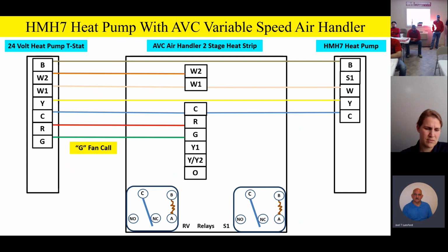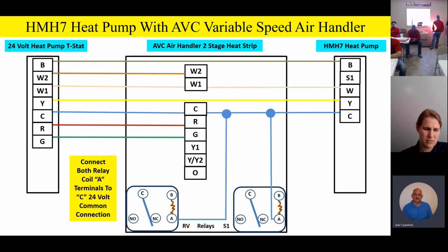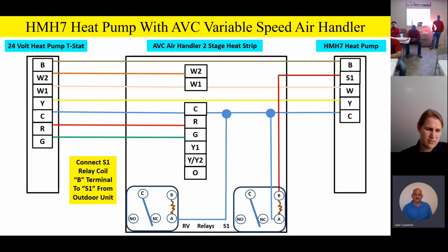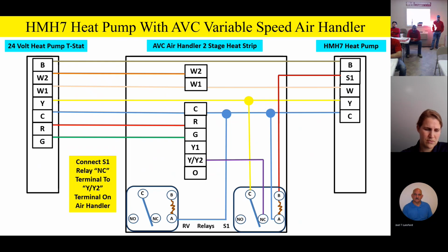Now, on the S1 relay, this is going to look familiar. You're going to notice that one side of the coil goes to common. You'd expect that, just like we had before. You'll notice that the other side of the coil on the S1 relay goes to S1, which makes sense. The common on the S1 relay is going to take 24 volts from the Y signal, just like we had before. The normally closed contact is going to go to Y2, second stage airflow. The normally open contact on the S1 relay will go to Y1, first stage airflow on the variable speed air handler.